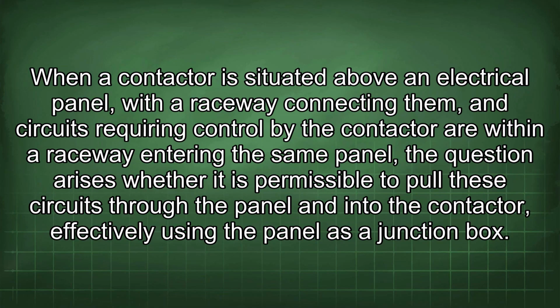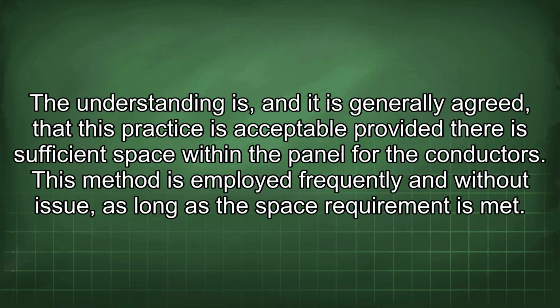When a contactor is situated above an electrical panel with a raceway connecting them, and circuits requiring control by the contactor are within a raceway entering the same panel, the question arises whether it is permissible to pull these circuits through the panel and into the contactor, effectively using the panel as a junction box. The understanding is, and it is generally agreed, that this practice is acceptable provided there is sufficient space within the panel for the conductors. This method is employed frequently and without issue, as long as the space requirement is met.